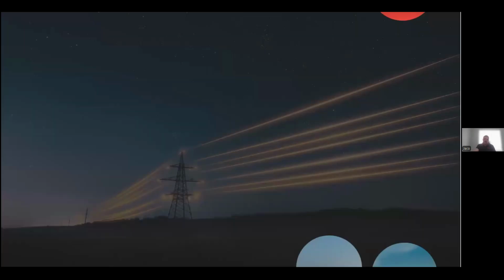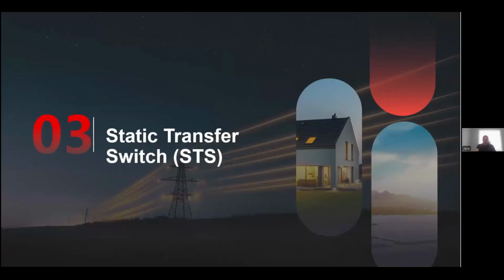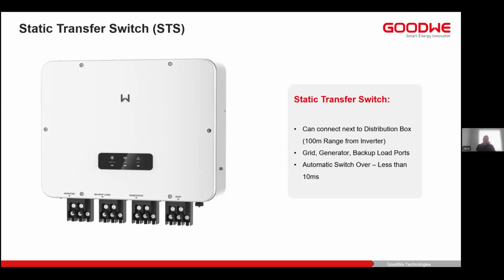Then taking a look at the static transfer switch. So the STS is a separate control mechanism that will enable a dedicated backup output or a generator input. The generator input can also double up as a big load output. So there's a programmable input and output. And then with the STS, we can achieve an automatic switchover that is less than 10 milliseconds.